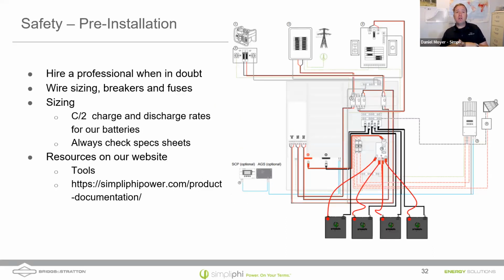The safest thing you can do when installing is make sure you're competent and your abilities are there to do this safely. I always say I know just enough to be dangerous. So if you can't pull a permit, you're not qualified - hire a professional. I always encourage everybody to permit all of these installations. Make sure you get somebody who knows how to interpret ampacity tables and breaker trip curves, and understands how to properly put overcurrent protection devices in the system, and who understands the maximum charge and discharge rate of our batteries.